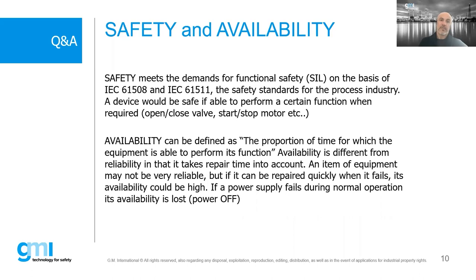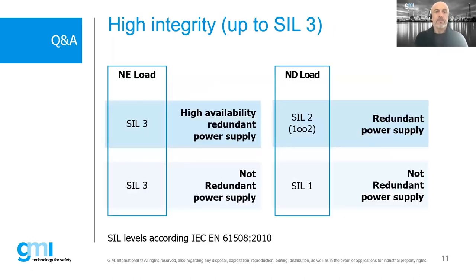Availability, however, is defined as the proportional time for which the equipment is able to perform its function. So availability is different from reliability, because this takes time to repair. An item of equipment may not be very reliable, but if it's repaired on time, its availability can of course be very high. Okay. There is also this one. It's the same slide we're repeating, and it highlights the necessary configuration for increasing the availability for normally energized, and also increasing the safety and availability for normally de-energized.